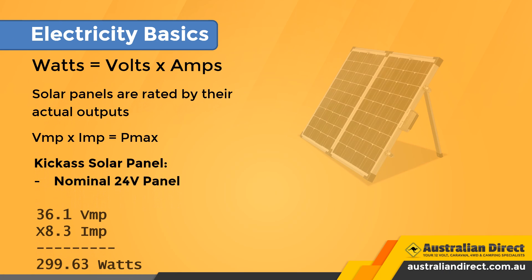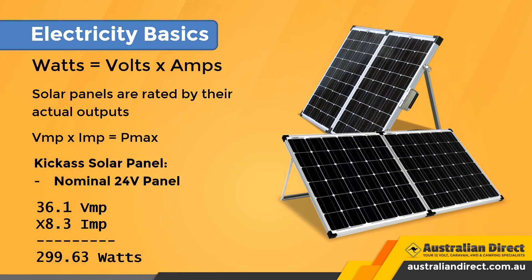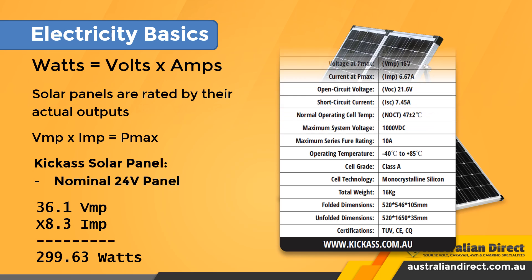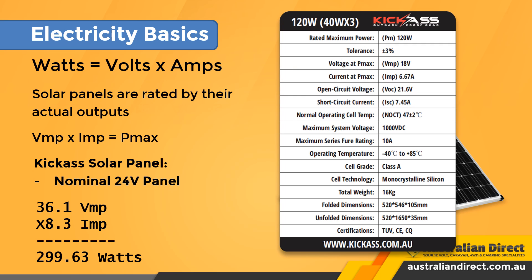Before I go further, I want to go over a quick reminder of power calculations. Solar panels are rated by their actual output when connected to a load. For instance, a generic 300W 24V nominal panel has an actual output of 36.1V and 8.3A. When you multiply them together you get the rated watts: 299.63 watts, rounded up to 300W. You can see the specs on the solar module's back or in its datasheet.